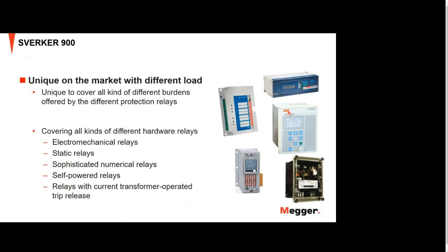You need to be quite accurate, and with the Sverker 900 we can deliver a very accurate current at very low current. For example, we can deliver 5 milliamps without any problems. So it's very sensitive and very accurate at low current, but it is very strong anyhow. So it's a combination of everything with the Sverker 900.